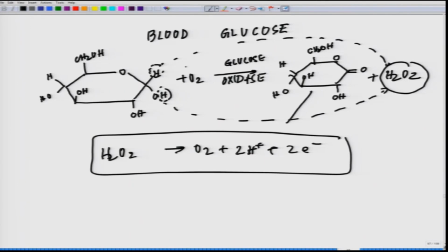So the oxygen has to come close to the enzyme layer. And here is the enzyme, glucose oxidase. In the presence of glucose oxidase, this is only going to happen if oxygen is available. If the oxygen concentration is low, the monitor responds as though the glucose concentration is very low.